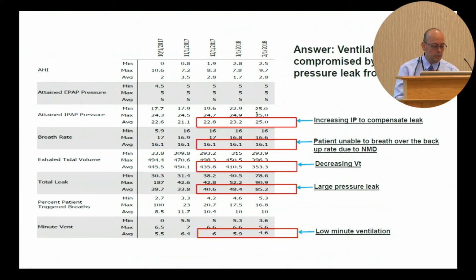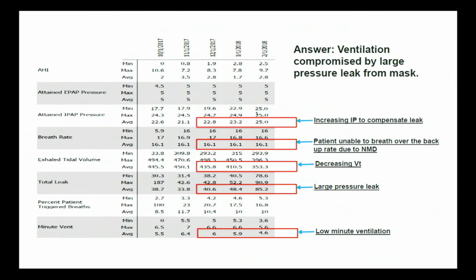This is a download from a patient on AVAPS. As the leak goes up, which here is the leak, 40, 48, 85, the IPAP is increasing to try to compensate for the loss in pressure. The tidal volume is decreasing, and your minute ventilation is going down. So it's very, very important to keep working on mask fitting.